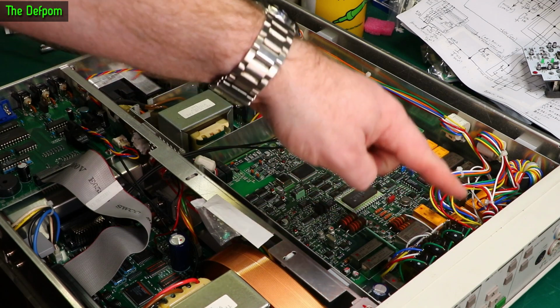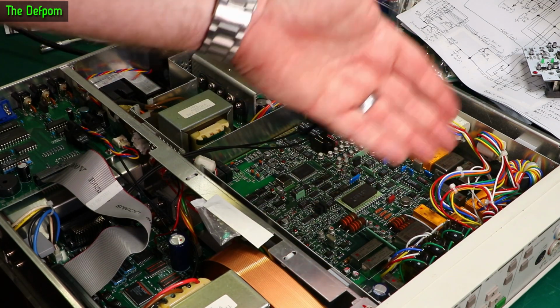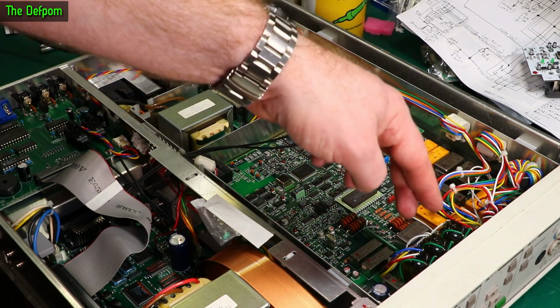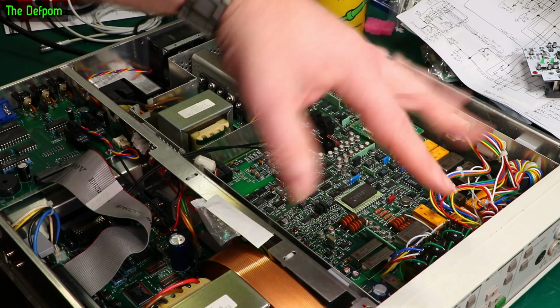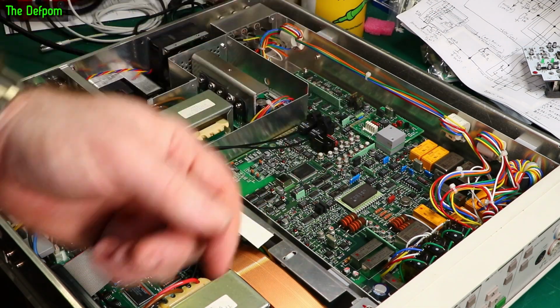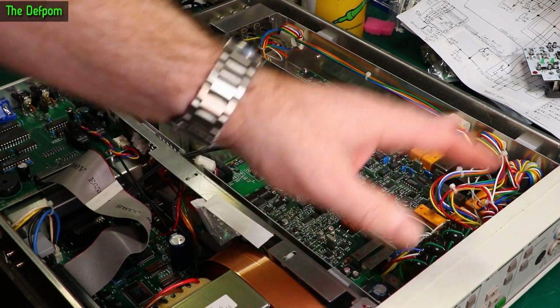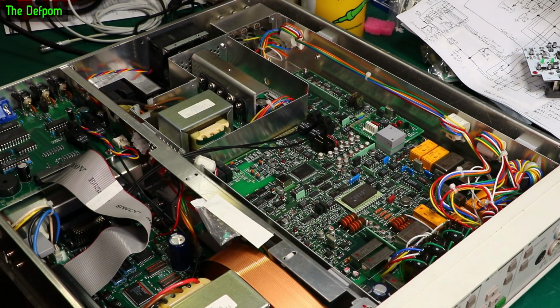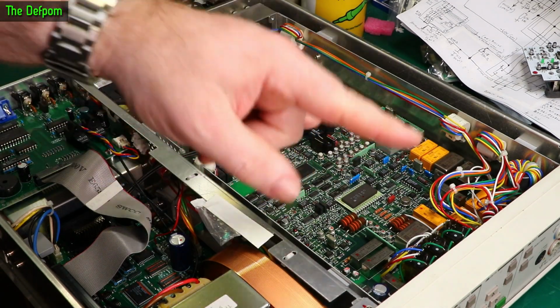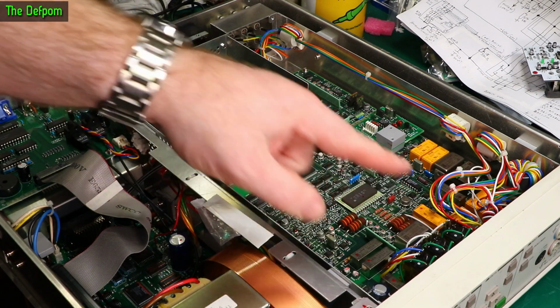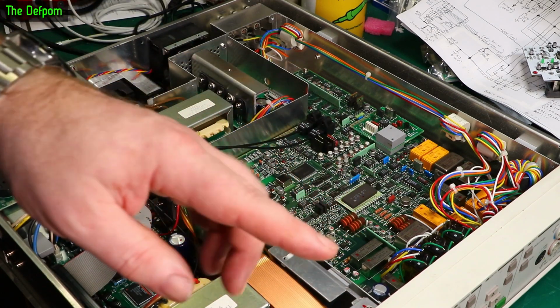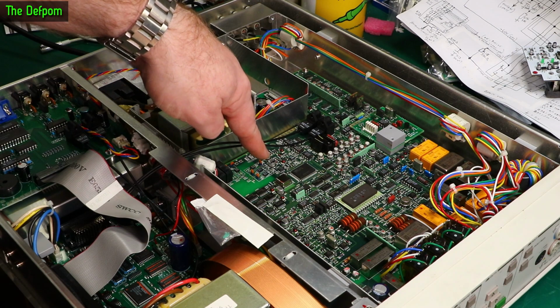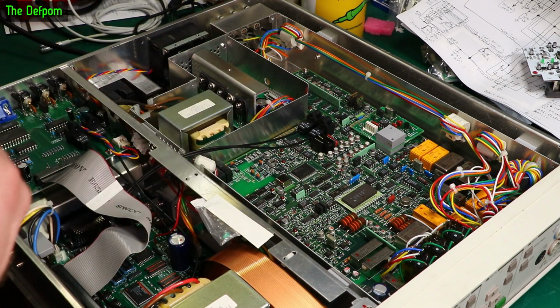This doesn't appear to be modified, so there are known modifications to these to fix the issue with this heating up, which causes a thermal EMF and that causes reading errors. And being an 8.5-digit meter, you want to minimise all those kinds of things. So there's two known errors with these, and my unit appears to have both of those errors from what I can see. I'm going to measure the voltages on this capacitor right now, and we'll see if it is backwards or not.